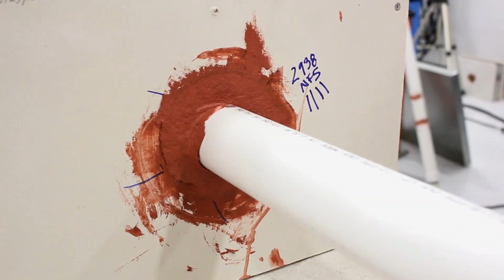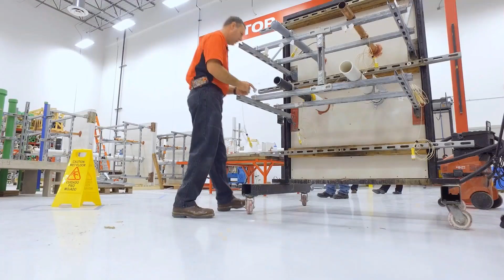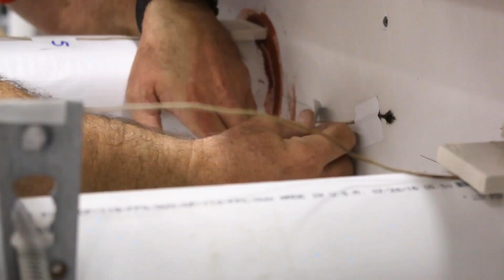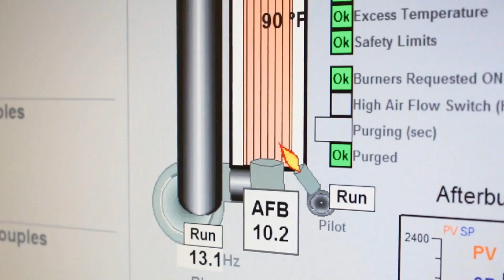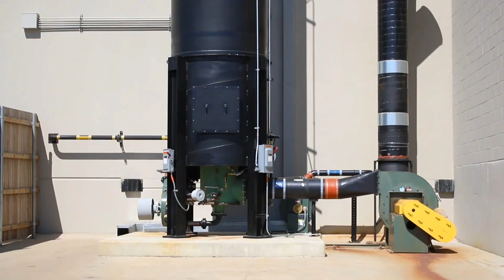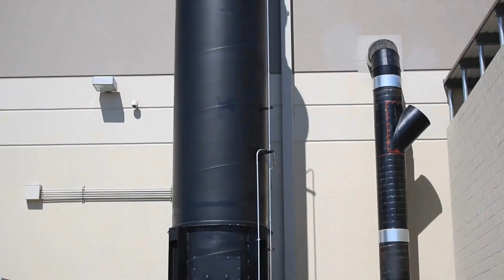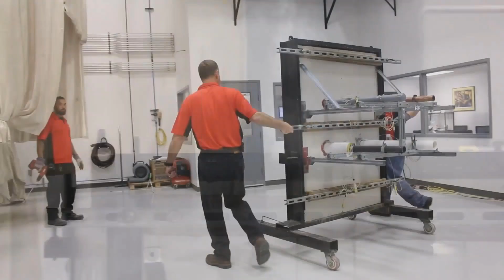In this example, the assemblies consist of plastic, insulated, and non-insulated pipe penetrations. Hilti Fire Stop solutions like FS1 mats and Fire Stop collars are installed around the pipe. Once the assemblies are built, we add thermocouples to measure heat transfer through the assembly and the pipes as required by the testing standards. As final touches are put on the assembly, technicians prepare the furnace and afterburner. The afterburner is a high-powered incinerator that burns the smoke and gases generated by the test itself.